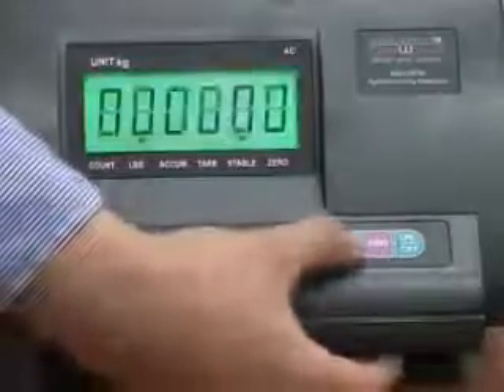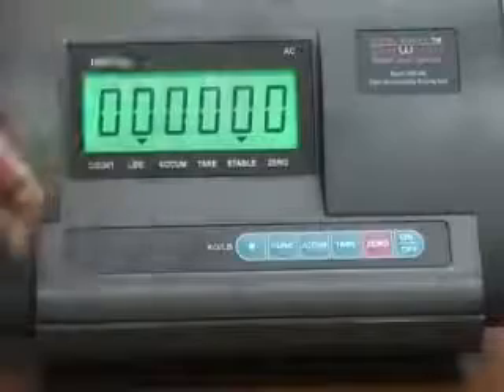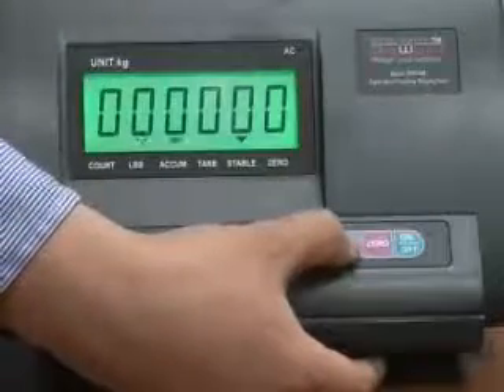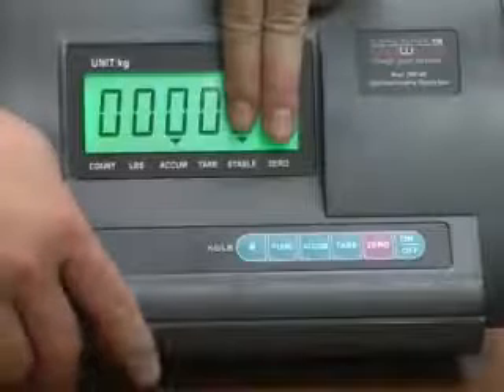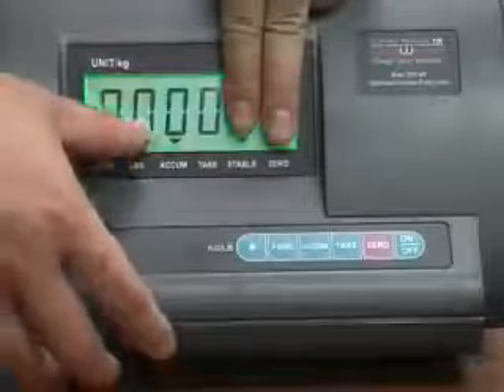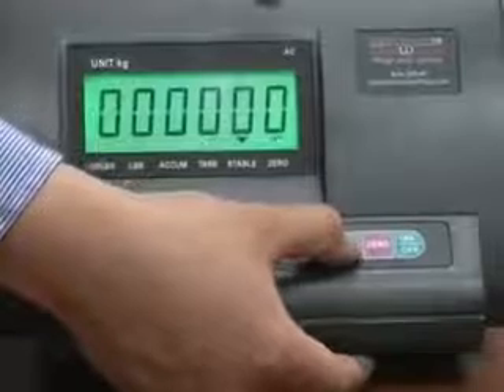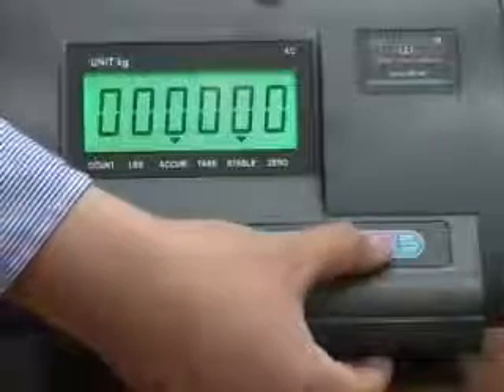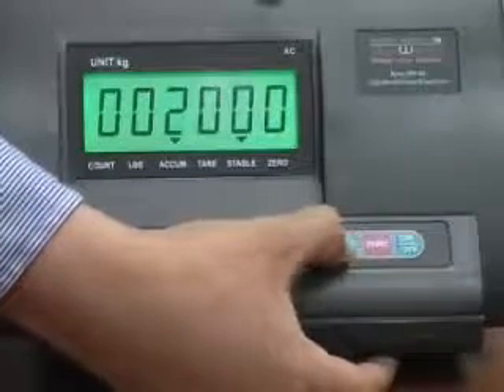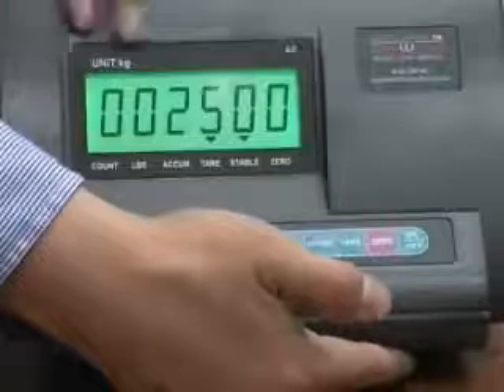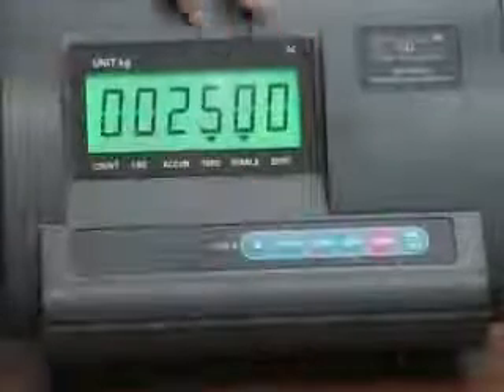To change the value, you can press the tare key, see all the zeros, then move the tare key to make it, in this case, 25 kg. Remember, we have 2 digits from right to left for decimals, so we need to make it 002500. To change values, first we need to move the little triangle to the digit we want to change. Then press the 0 key to change the value. Change this to be 5. Remember, everything here is in kg, no pounds.